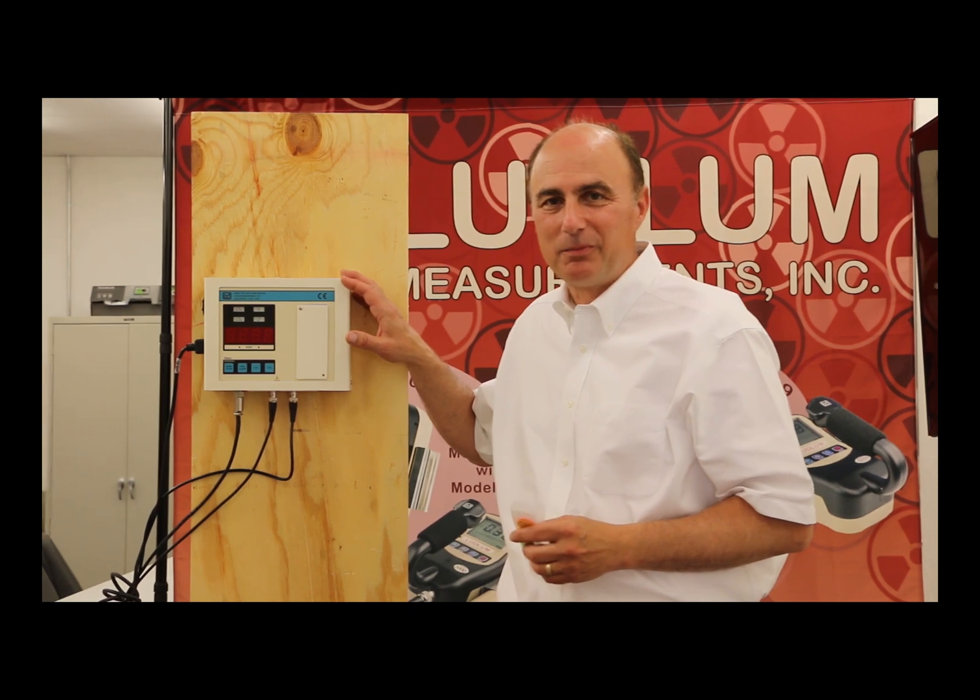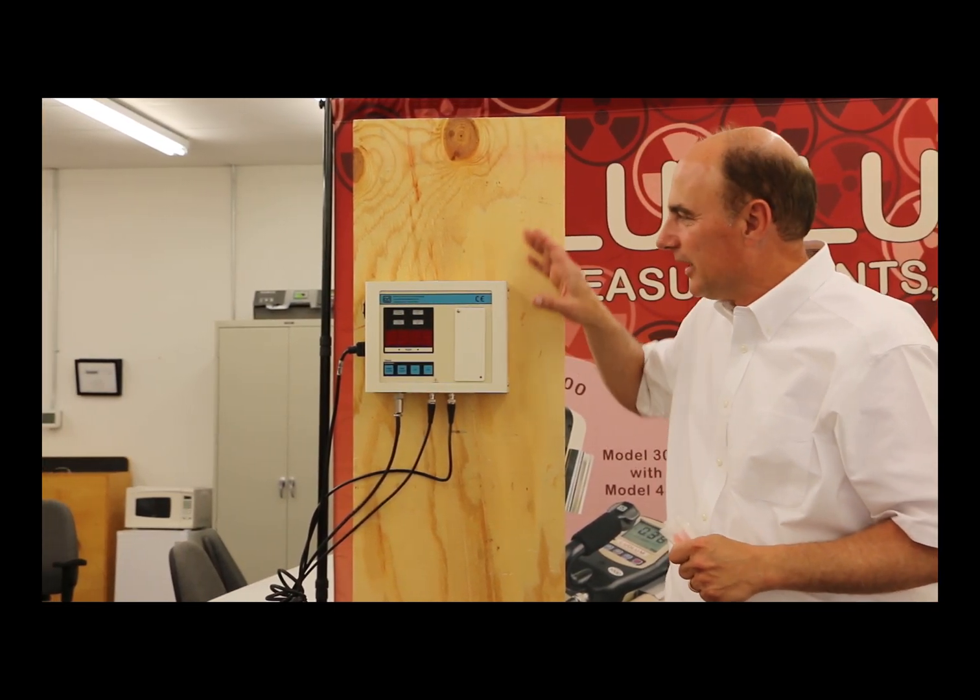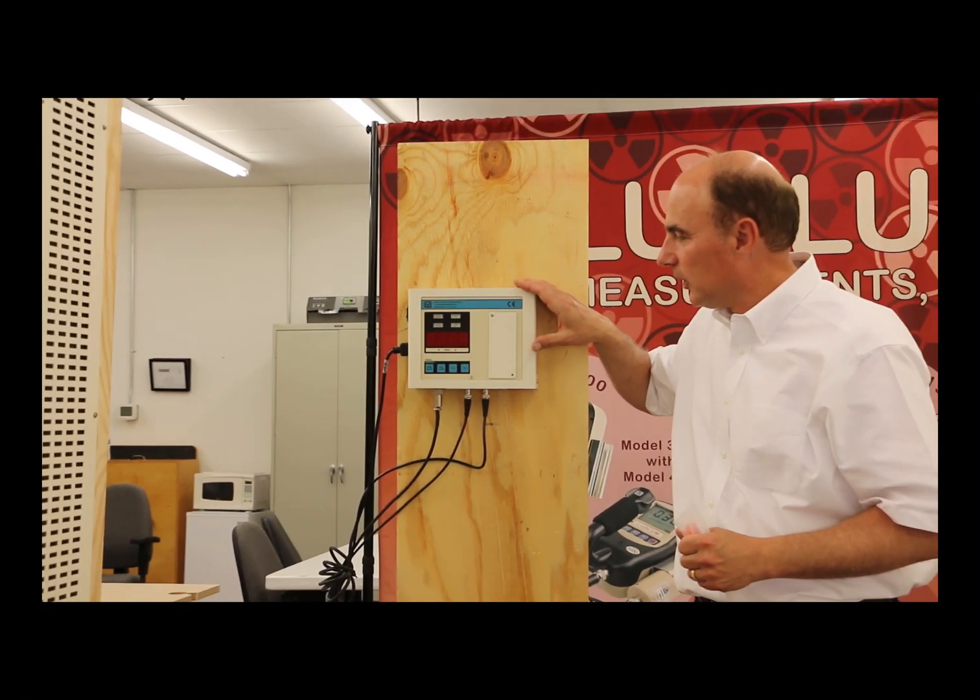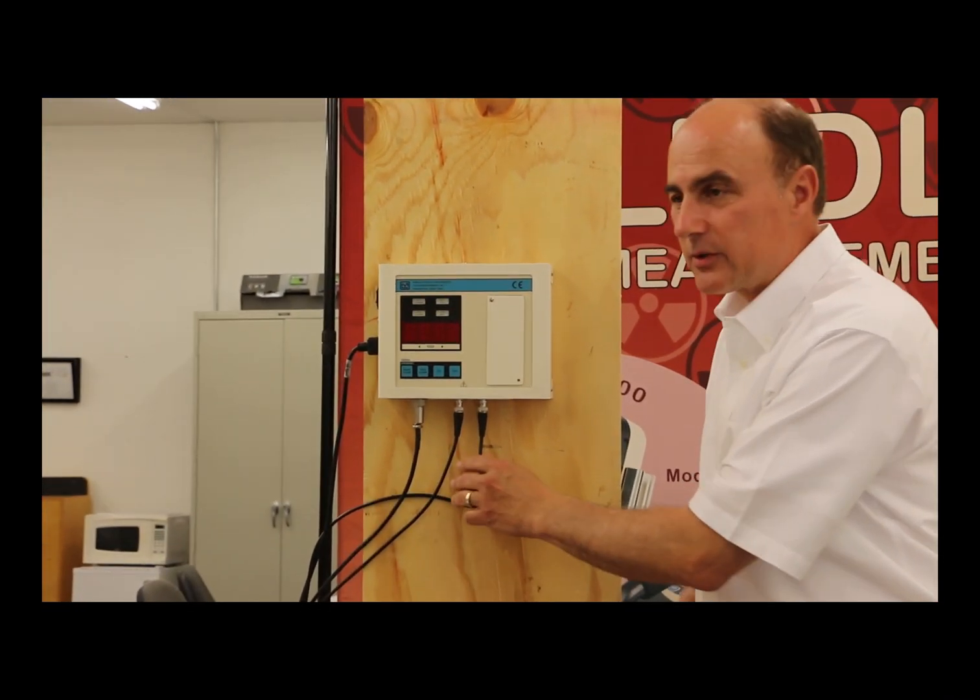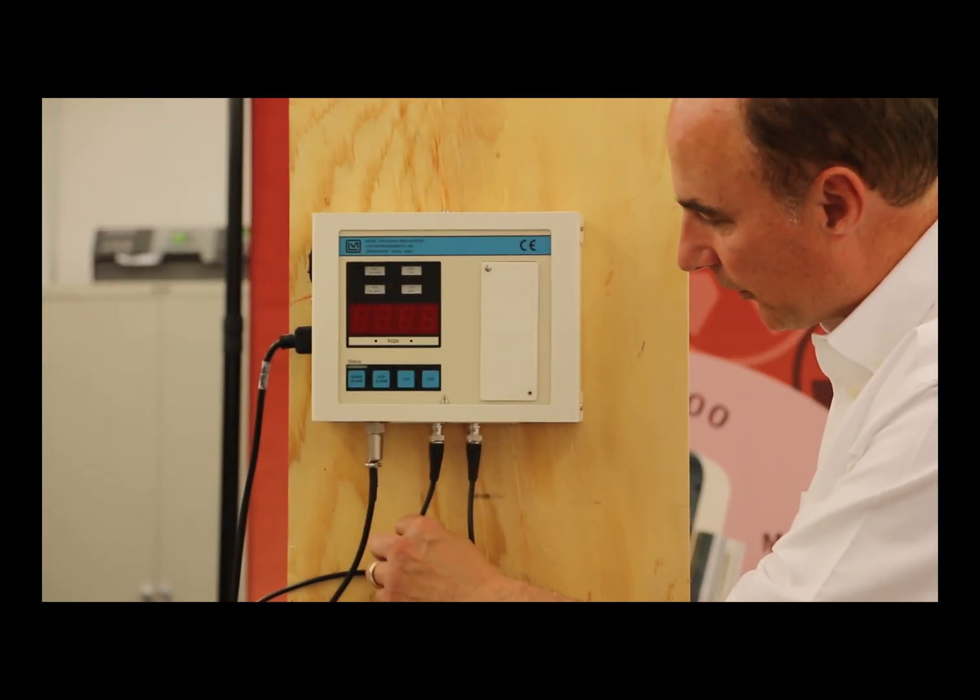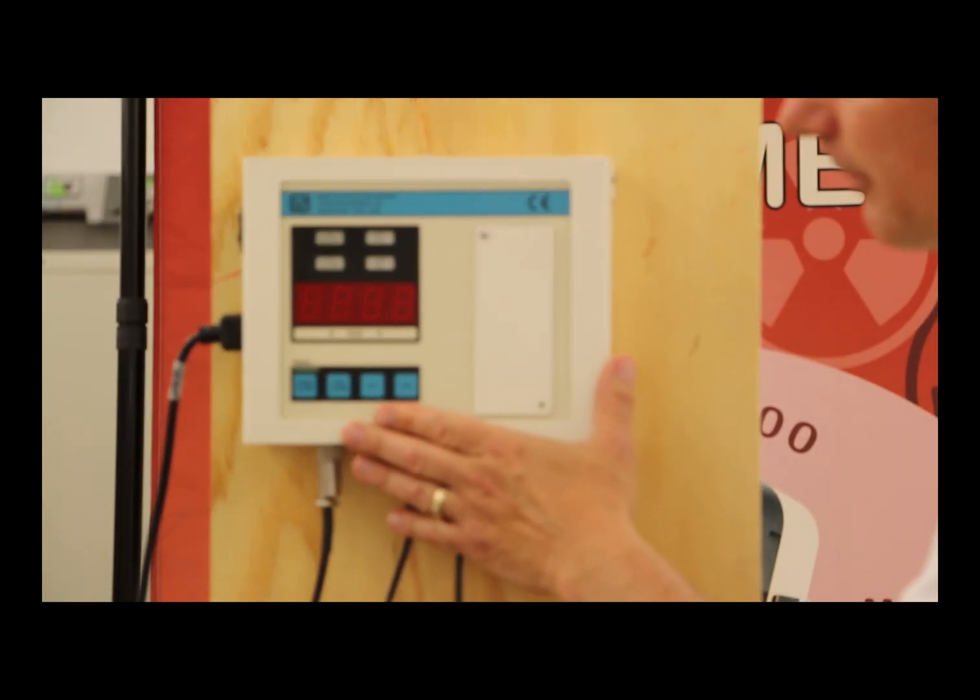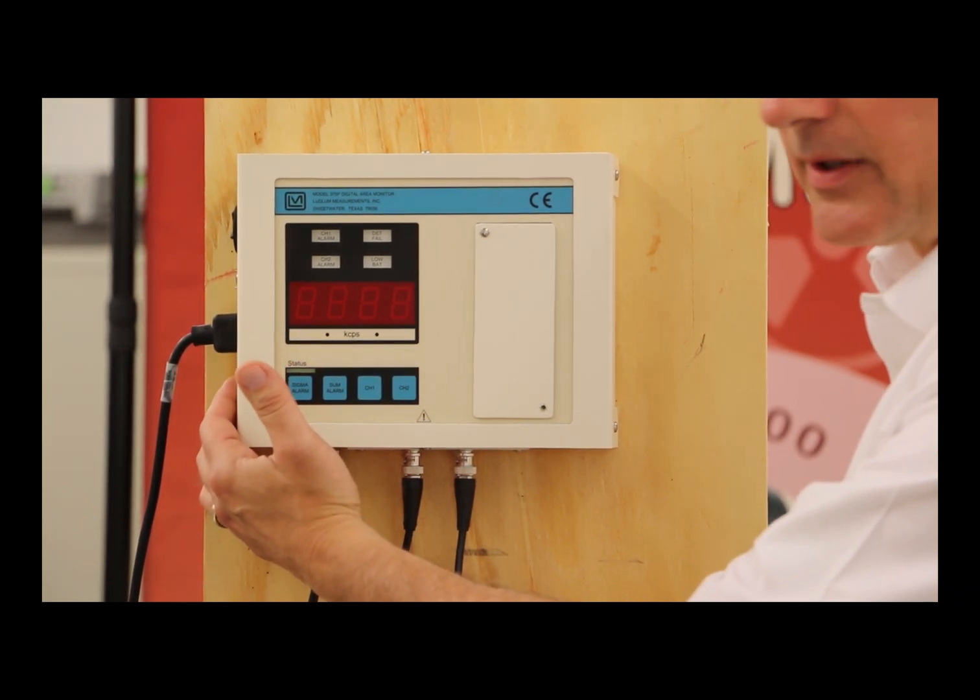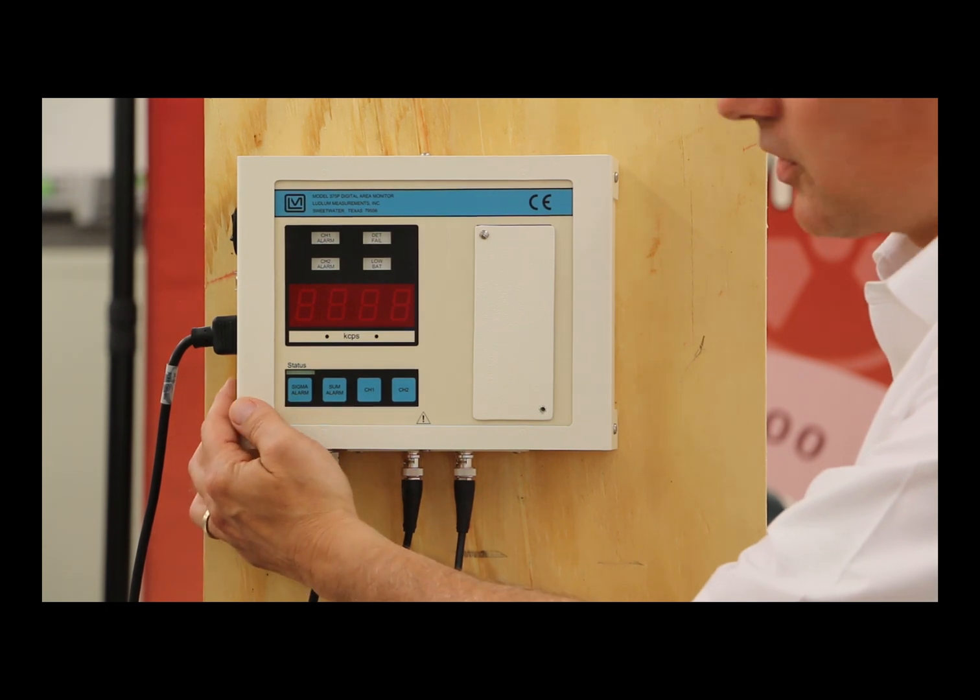Now let's jump into the operation of the Model 375P-336. As I mentioned before, it includes a 375 monitor, which will collect counts from two detectors, two scintillation detectors, which you can see the inputs here for channel one and channel two. It feeds them into the monitor where it sums the counts and how much radiation we're collecting. I'm going to switch this on.